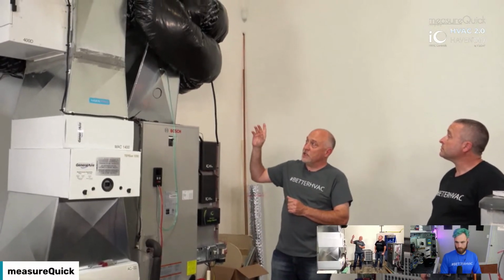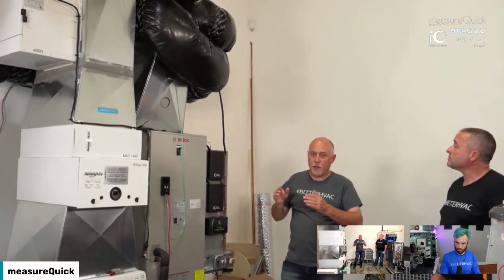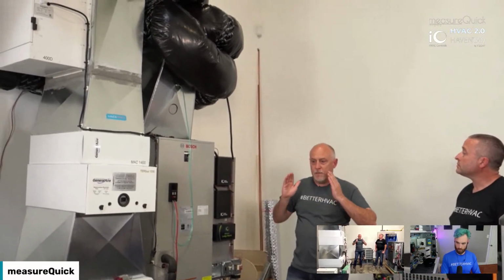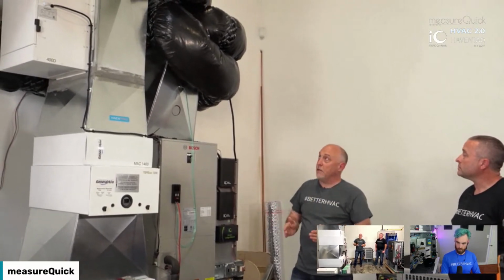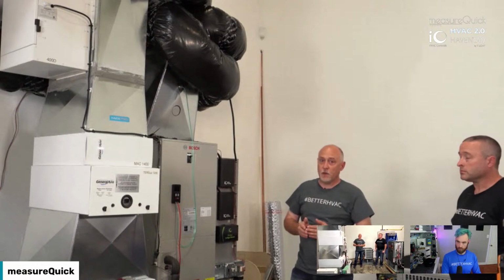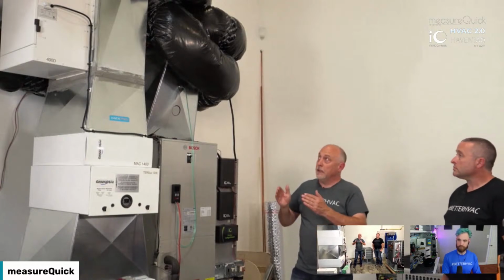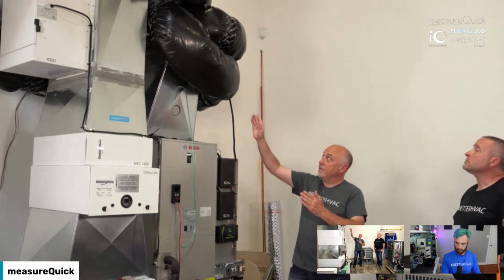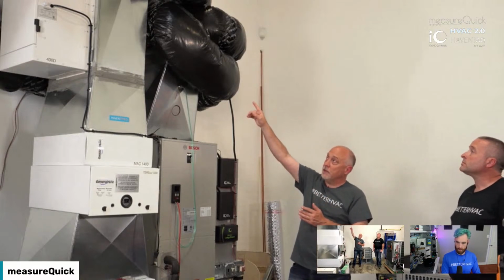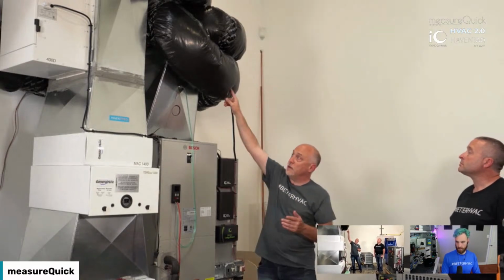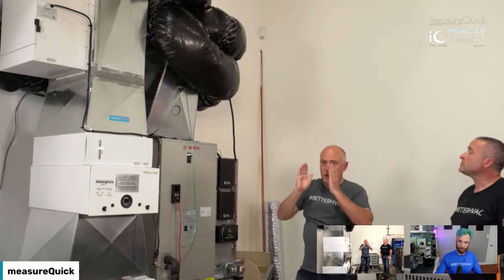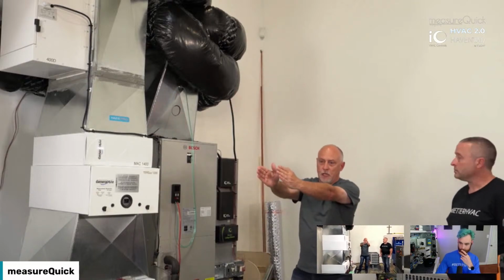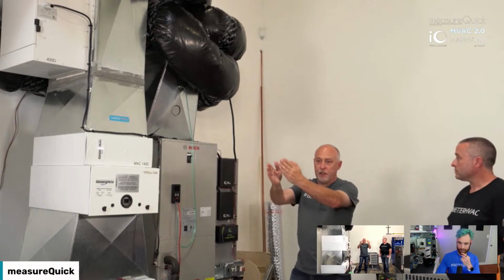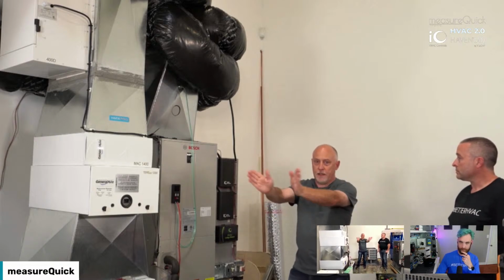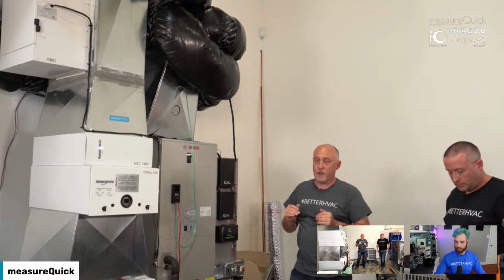We had to set this up with two duct systems, and part of the reason is so we can blow air across the room. Thank you, Michael Hausch, for designing this for us—it was a huge help getting everything sized. Basically we have 4 8-inch supply runs, round pipes that blow straight across the room. They carry the air about 35 feet, hopefully entraining air behind it, so when the air shoots out it rolls back in and pulls back into the returns.